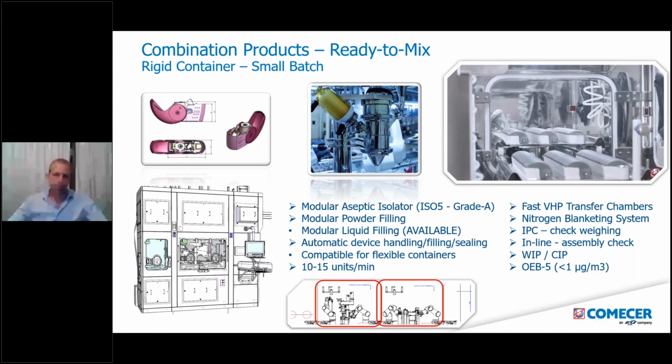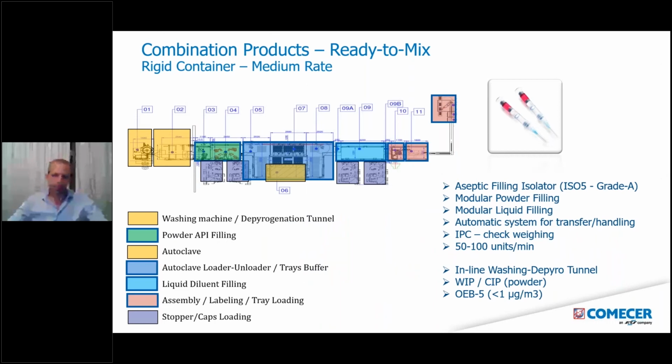The next one that I'm going to show you is a medium rate filling line, for commercial production, made for filling dual chamber syringes. The line is designed to fill a single type of container with two different chambers, one for the powder and one for the liquid.